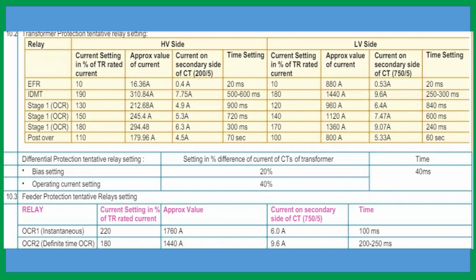Differential protection, bias setting, they have told 20% and operating current setting is 40%. I have told differential relay and bias setting possibly. I will see it later. I will tell you what is bias setting and what is operating current setting. Then current setting percentage of transformer rated current: OCR 1 instantaneous 220%. OCR 1 current setting at 220%.